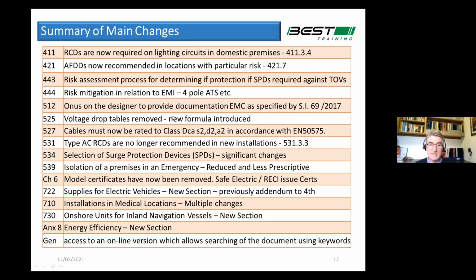And in fact, when we get into chapter 5, it tells us there's an onus on the designer to provide documentation where requested to prove compliance with the EMC directive. Bit of a tall order. You're designing an electrical installation. You can't really test it fully for EMC compliance, but you certainly can follow the guidance in part 444. And if you do that, in my view, you're really doing the best you can to make sure the electrical installation is not going to cause interference elsewhere.